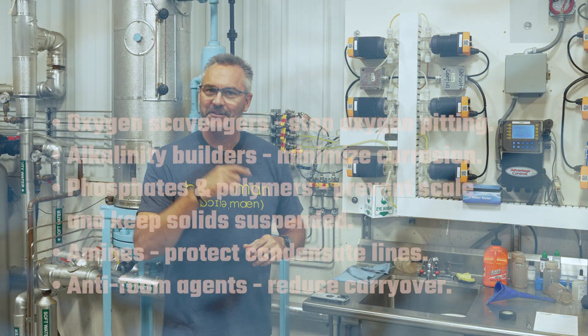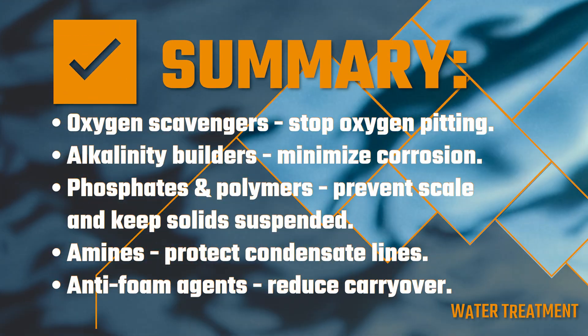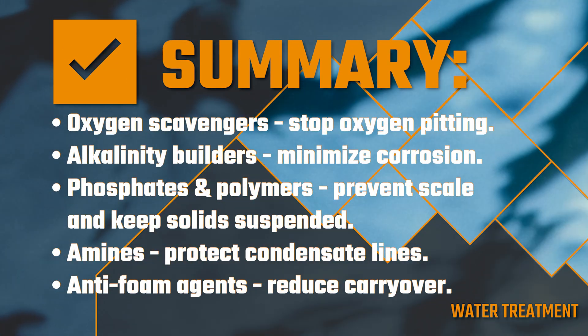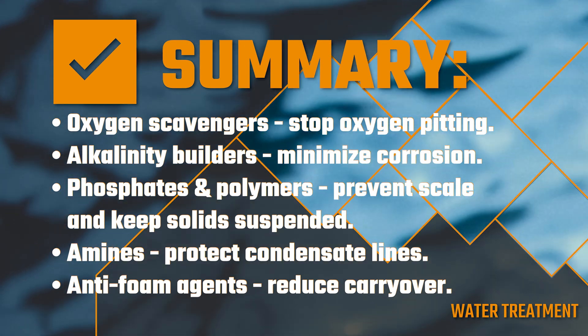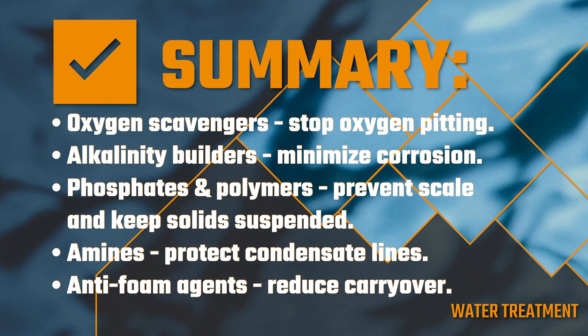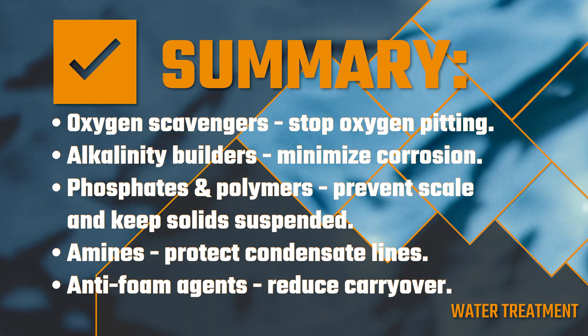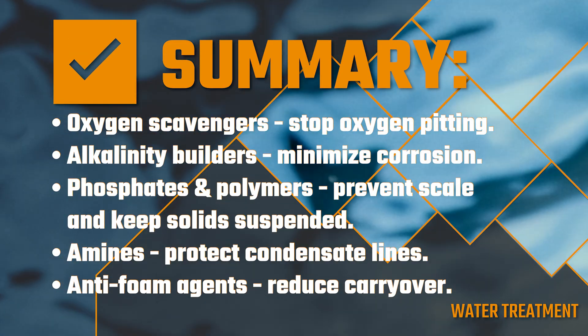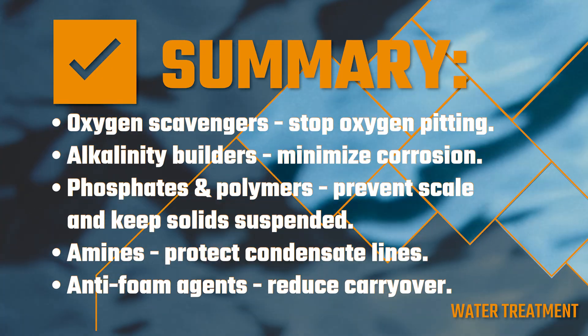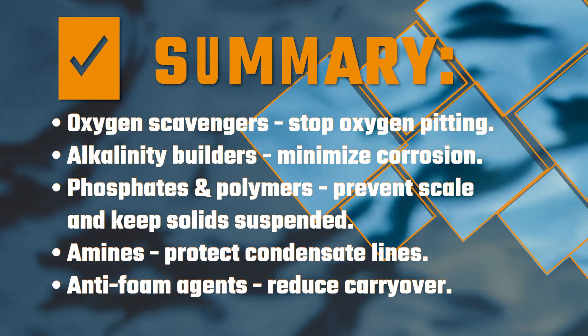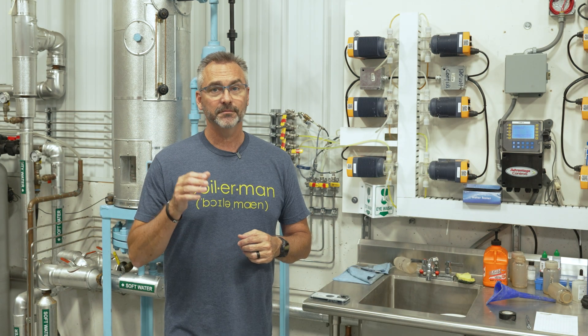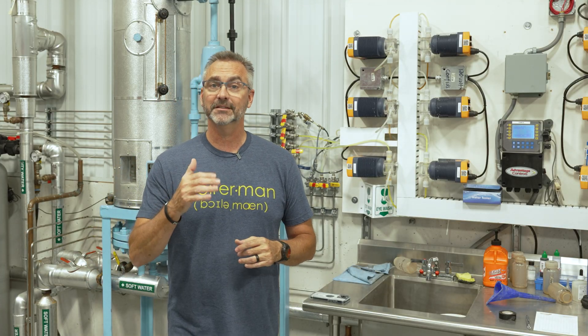In summary: oxygen scavengers stop oxygen pitting. Alkalinity builders and pH control agents minimize corrosion. Phosphates and polymers prevent scale and keep solids suspended, Amines protect condensate lines. Anti-foam agents reduce carryover. Together, these chemicals protect the boiler, the piping, and the steam system from corrosion, scaling, and carryover — maximizing efficiency and equipment life.